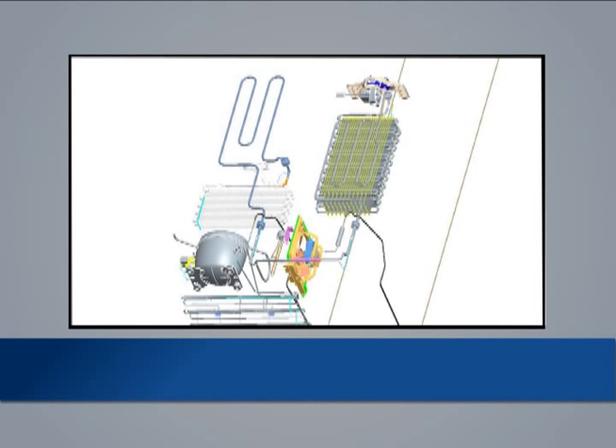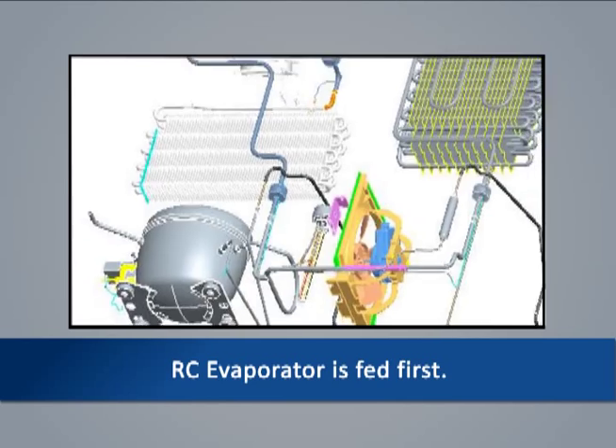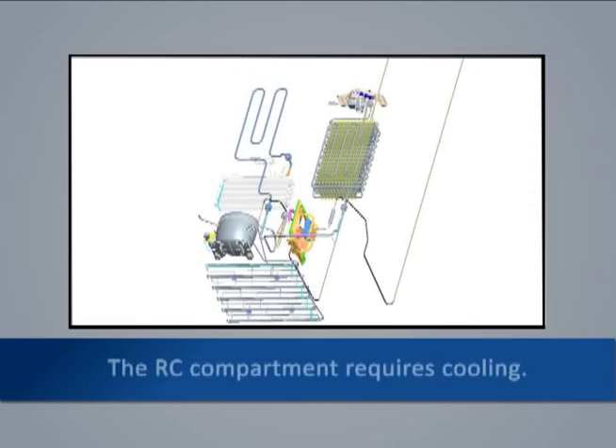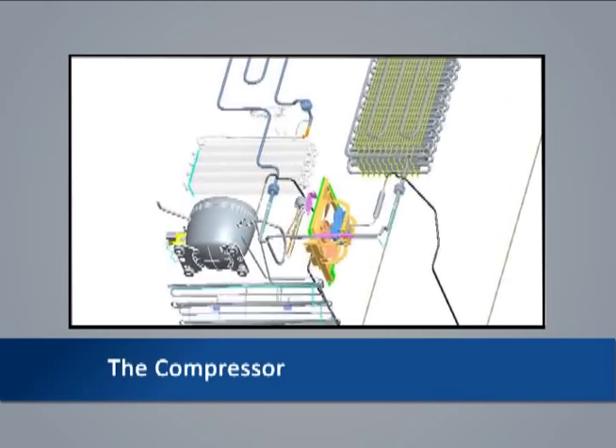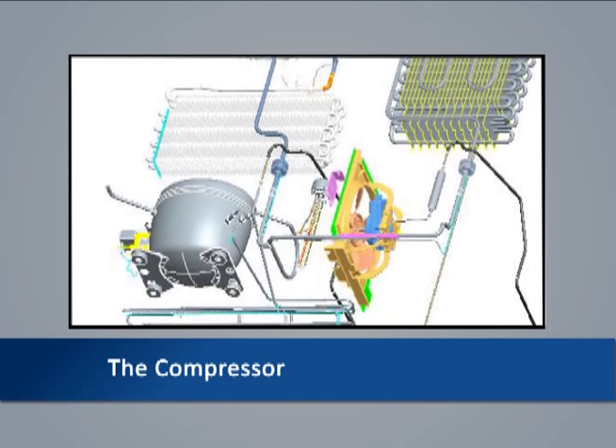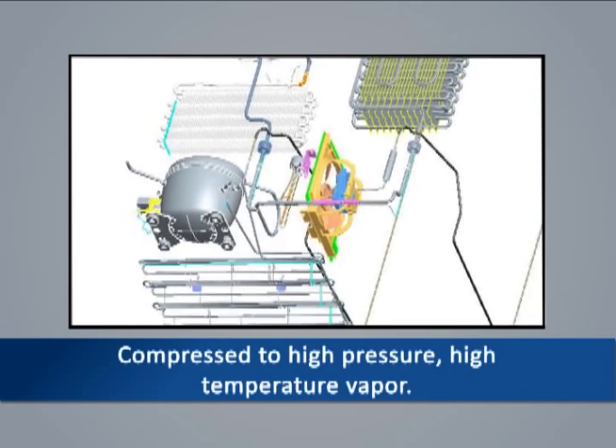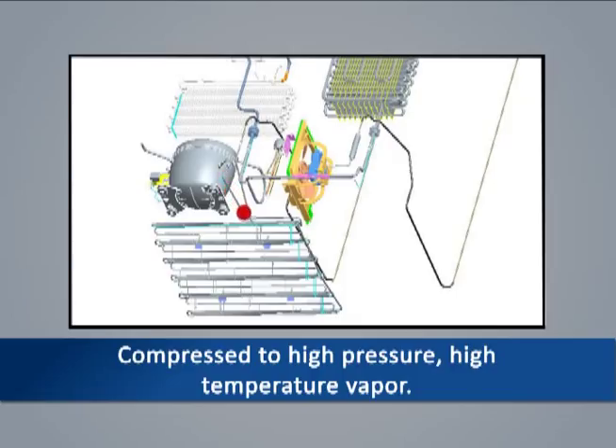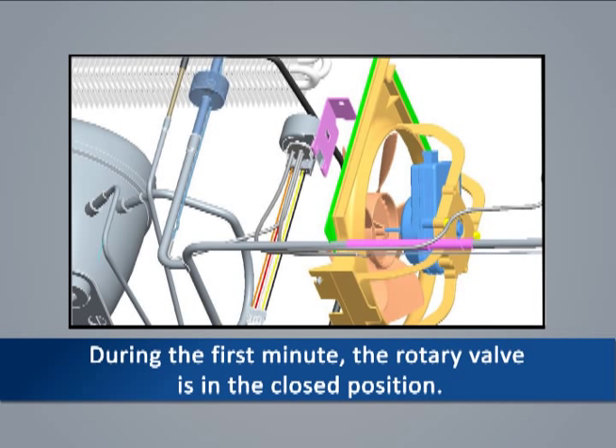On initial startup of a dual evaporator system, the RC evaporator is fed first. After that, the control supplies refrigerant to the evaporator most in need of cooling. Assume the board has determined the RC compartment requires cooling. Starting at the compressor, the compressor and condenser fans are energized by the control board. The compressor pulls low pressure, low temperature refrigerant vapor through the suction line from the RC evaporator, compresses it to a high pressure, high temperature vapor, and it exits through the discharge line to the condenser. During the first minute of compressor operation, the rotary valve is in the closed position.